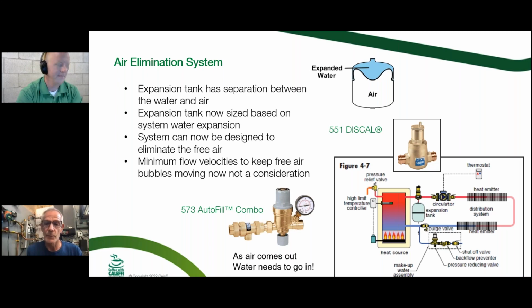So these micro bubble resorbers, like you see the Caleffi Discal that we just talked about on the top, they're going to get 97% of the air out of your system within the first couple hours. As long as all the fluid is going past that device, you're going to grab it, whether it's hot, whether it's cold, whether it's big, whether it's small. So that's really the best way to get the system evacuated quickly, efficiently.